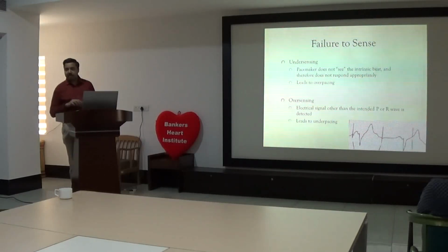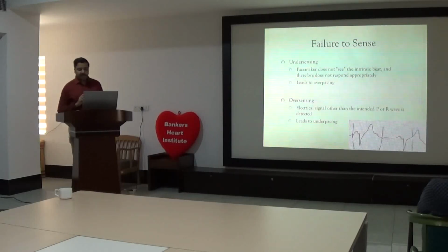Vice versa, oversensing. Now we will discuss what the causes of oversensing are, but one commonest cause in a temporary pacemaker is shivering. Shivering and skeletal muscular contraction. This skeletal muscle contraction is sometimes sensed as cardiac activity, and the pacemaker oversenses the activity of skeletal muscle and it won't pace. So oversensing will lead to underpacing. Keep it simple.